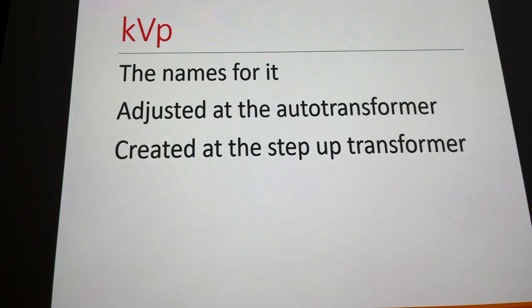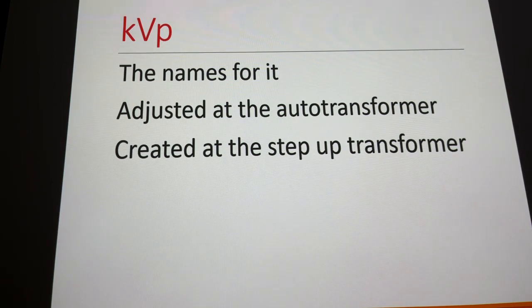We detect how much voltage we're actually using with a pre-reading KVP meter. It's called a pre-reading KVP meter because we don't have KVP yet — we're just using voltage. Since we have a set turns ratio on the high voltage transformer, if the voltage is correct on the auto transformer, we know it will be right once it passes through and becomes KVP. KVP — also called potential difference, electric potential — is adjusted at the auto transformer but not created until the high voltage transformer.